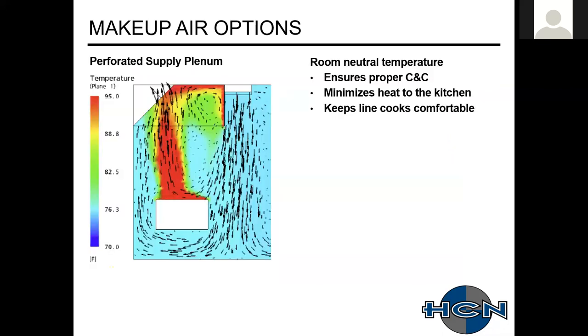Here's a CFD showing that blast system, how everything's at the right temperatures and the right velocities. That makeup air plenum is putting that air right back into the hood, not affecting the cooking staff. I think we're running right around 75 degrees for this.